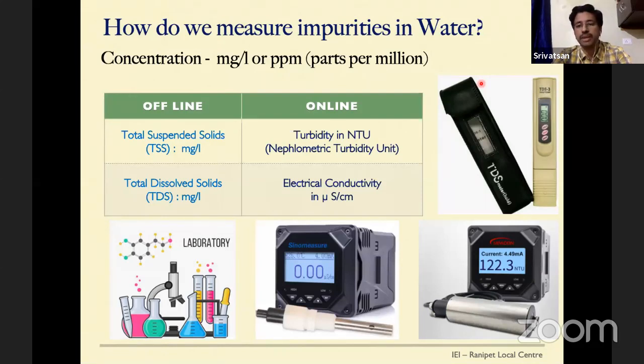So for suspended particles, to measure online, we use a turbidity meter. Turbidity is nothing but the amount of haziness present in water: how much light the particles present in water can diffract. This is measured in nephelometric turbidity units, or NTU. Basically, the more particles there are, the more diffraction of light, and the higher the turbidity. Bigger particles will also have more light diffraction and show high turbidity values.